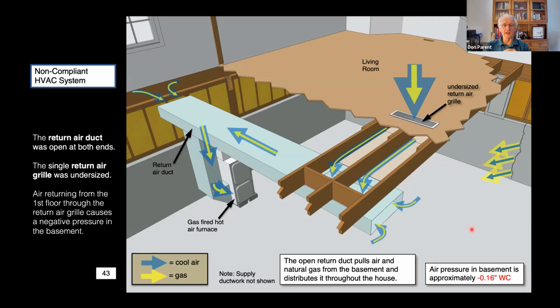What you also see here is a crack. There's a crack in the foundation right here. And obviously we've got these arrows indicating, yeah, maybe there's some gas coming through here. We don't know. So the grill in the floor was the only means by which air could get back down to the furnace in the basement for recirculation. Yet a quick analysis of that grill indicated that it's approximately a factor of 3 too small for the amount of air that needed to be returned.